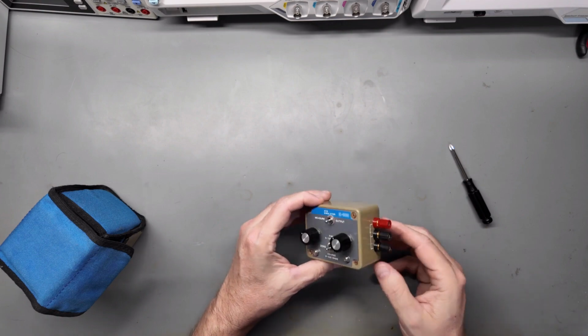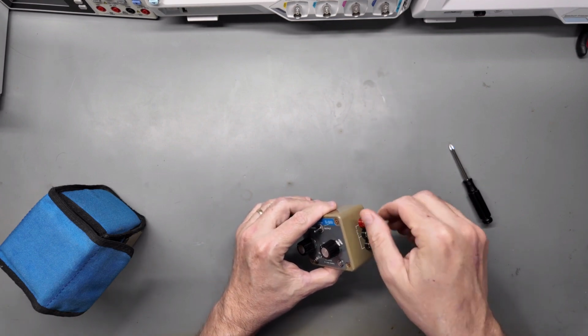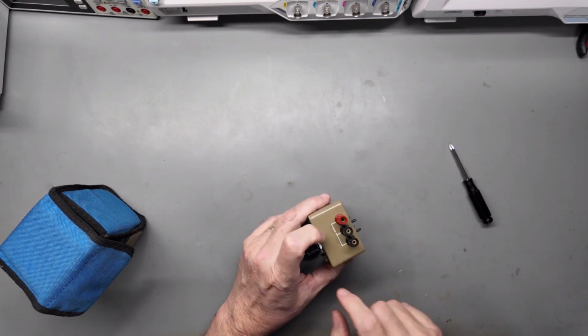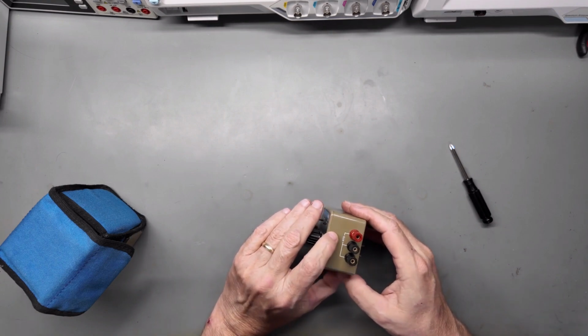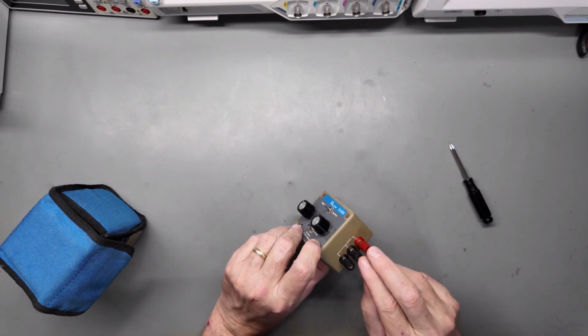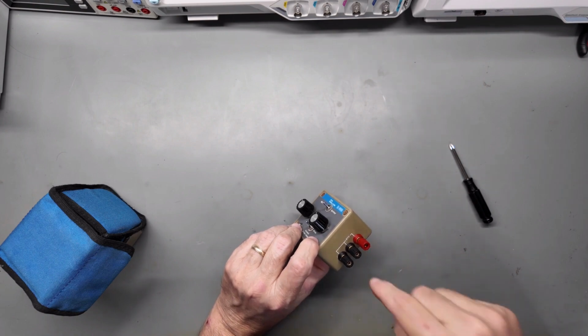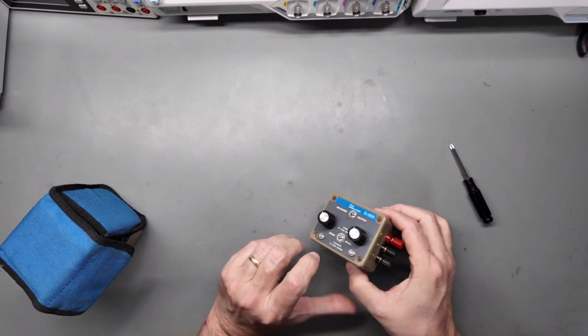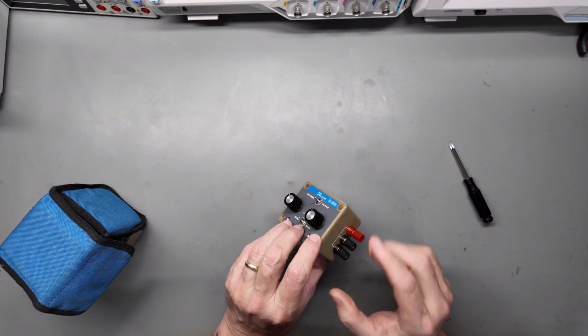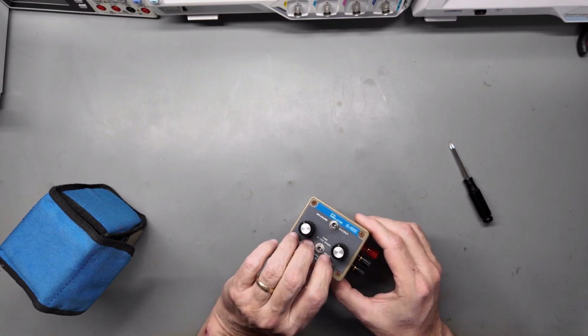Now, you hooked your piece of equipment to here, and this was your RTD right here. This is where you simulated it. The outputs here simulated having a temperature sensor right there. Based on what you set here, your equipment would recognize that resistance as a certain temperature.